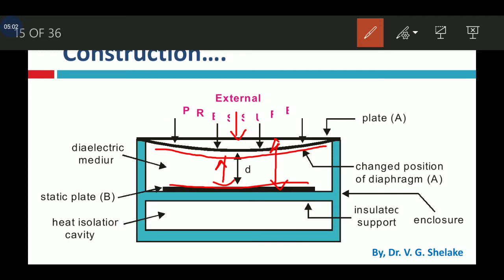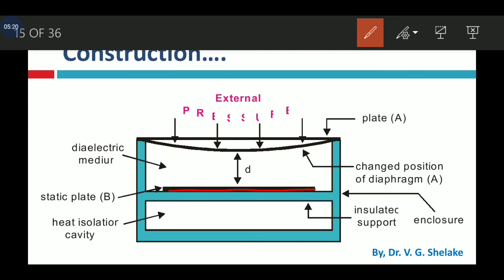The total assembly is enclosed in an insulating enclosure made of plastic or ceramic, with insulated support for the static plate. When plate A changes its position, the capacitance value changes. There is a heat isolation cavity because changes in temperature may also affect the capacitance value. External pressure is converted into an equivalent voltage. It is a passive transducer because storing charges requires an external battery or supply.